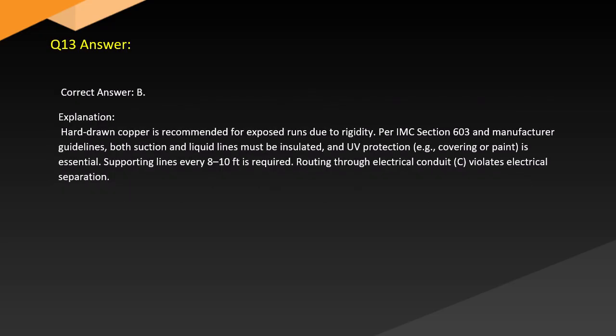Answer. Correct answer: B. Explanation. Hard-drawn copper is recommended for exposed runs due to rigidity. Per IMC Section 603 and manufacturer guidelines, both suction and liquid lines must be insulated and UV protected. E.g., covering or paint is essential. Supporting lines every 8 to 10 feet is required. Routing through electrical conduit, C, violates electrical separation.